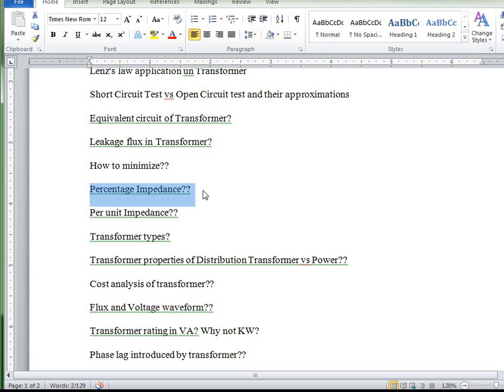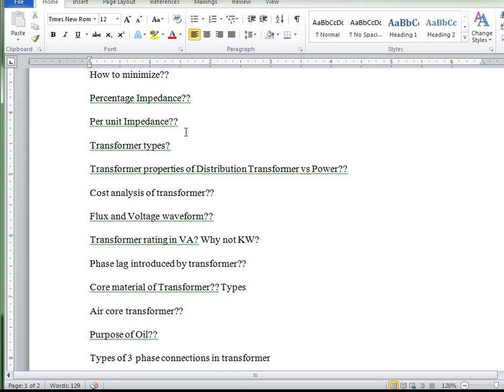But for a distribution transformer, because you are converting from 11 kV to 400 volts, if the impedance here is kept at 6 or 7% instead of 4%, this means there is more voltage drop. You won't get 220 or 230 volts, you'll get 210 or maybe 190 something. So there will be more voltage drop. This value of percentage Z for distribution transformers, at least in Lahore or overall Punjab, is kept at 4%, and for power transformers it's on the higher side so that the series impedance is changed accordingly.